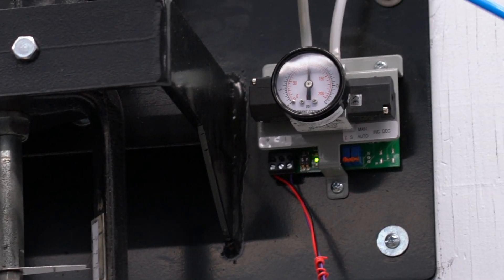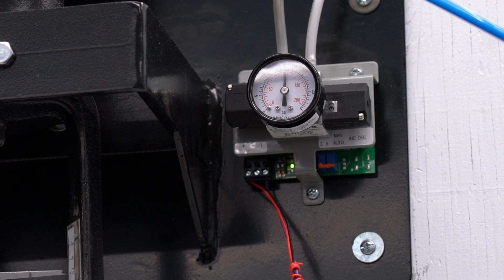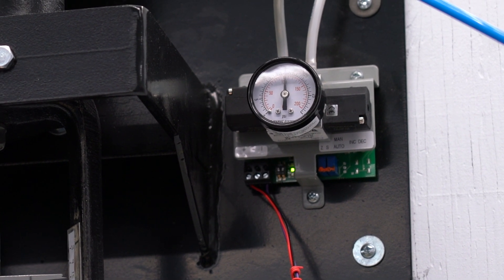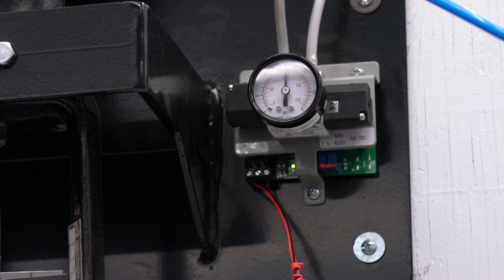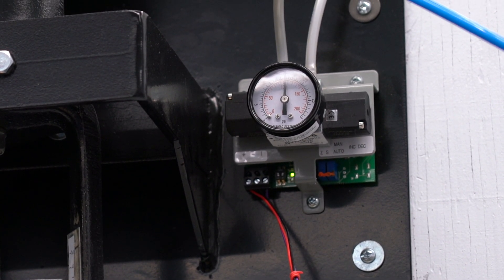And I'm going to reduce the voltage. So if I go from 10 down to 0 volts, I should go from 15 to 3 psi. So I'm going to start lowering the voltage and you're going to see that valve change.